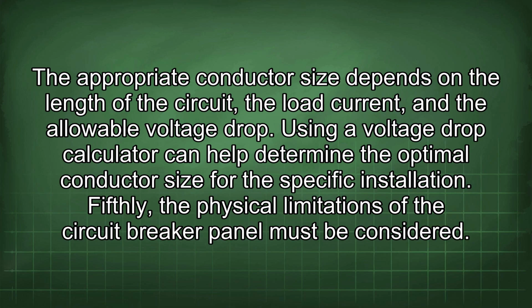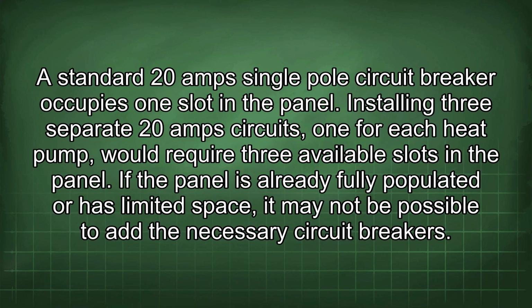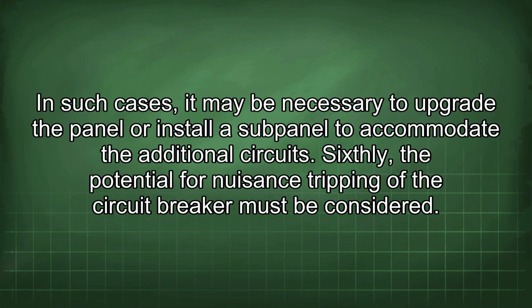Fifthly, the physical limitations of the circuit breaker panel must be considered. A standard 20 amp single pole circuit breaker occupies 1 slot in the panel. Installing 3 separate 20 amp circuits, one for each heat pump, would require 3 available slots in the panel. If the panel is already fully populated or has limited space, it may not be possible to add the necessary circuit breakers.